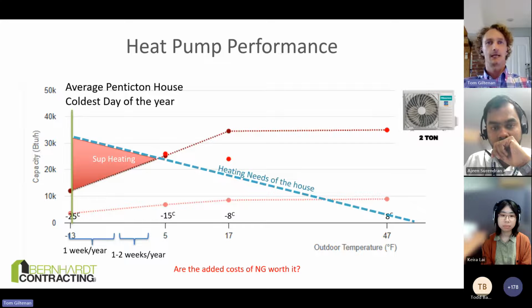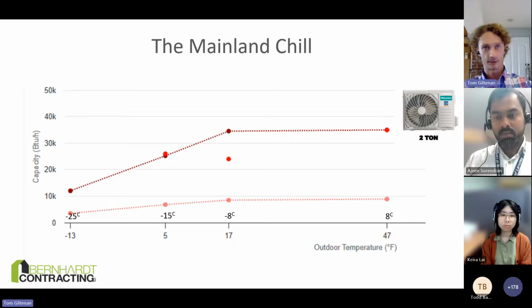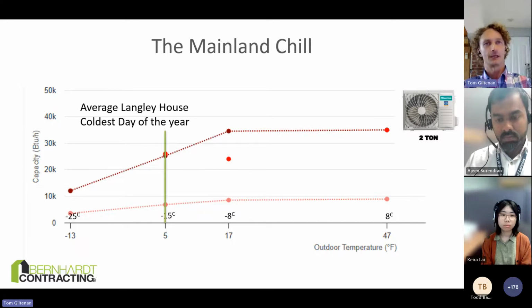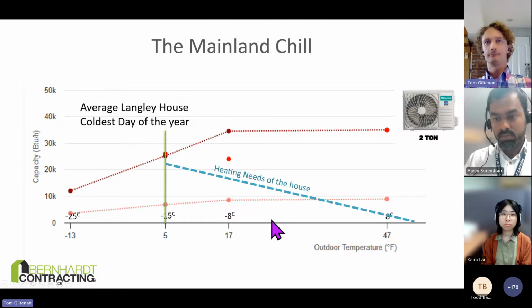And that is a question for your individual clients. Now, if we look at the same model, same type of systems in the mainland, we have a Langley house, coldest day, 2.5% is about -15. That's the coldest day of the year. And then if we use the same heat pump in the same system, we meet that. We will not need supplemental heat. It will never be a requirement.